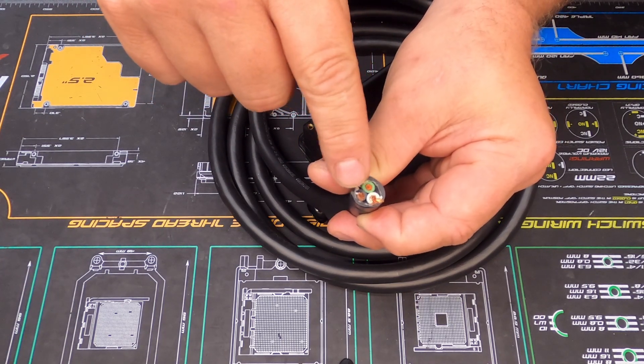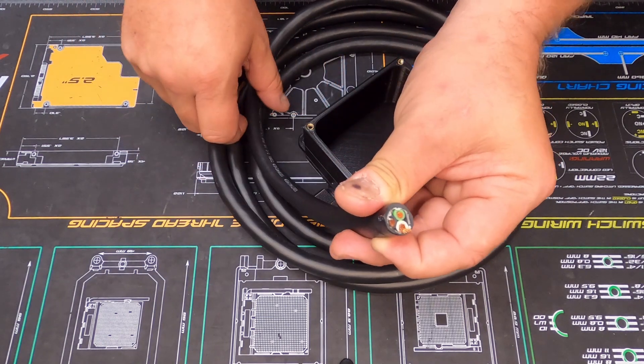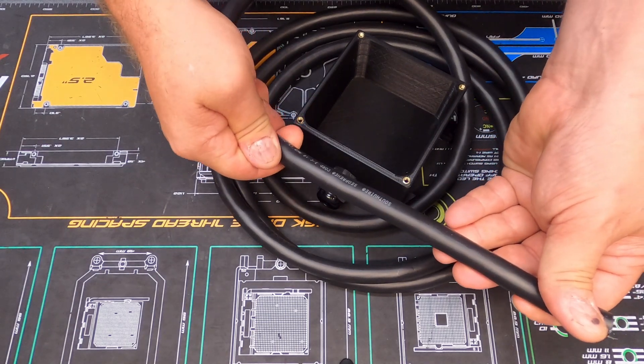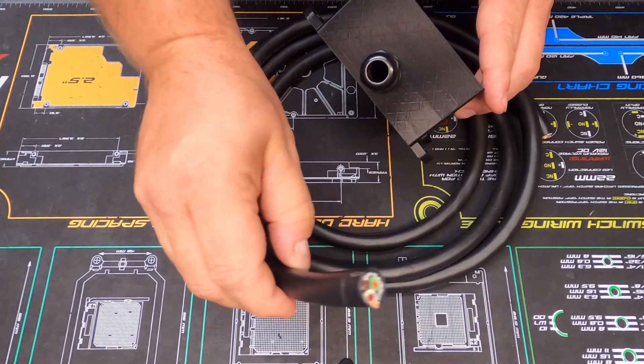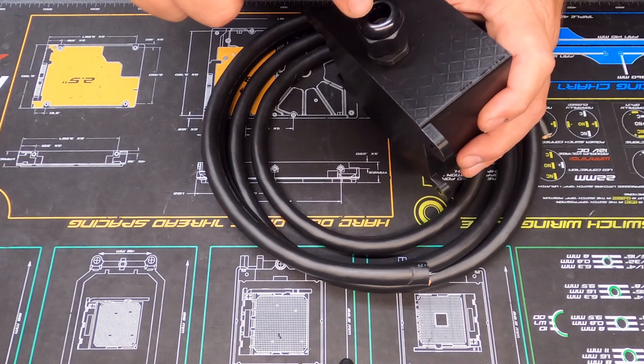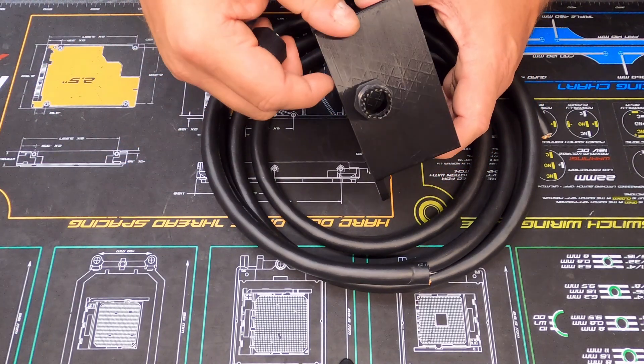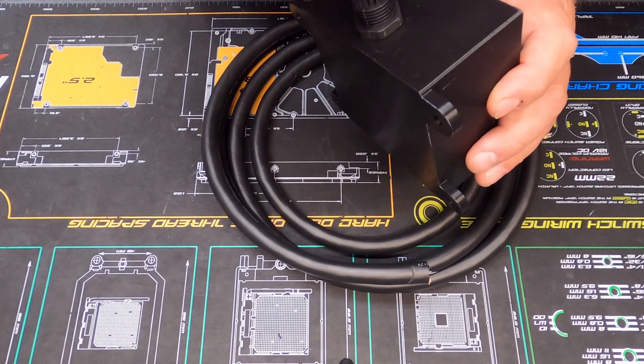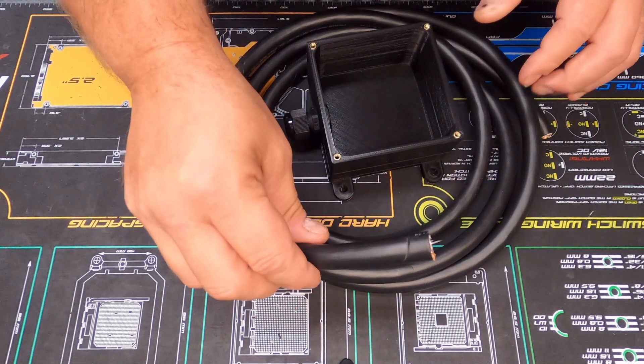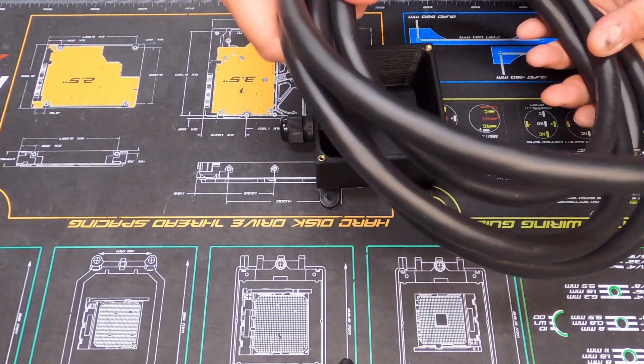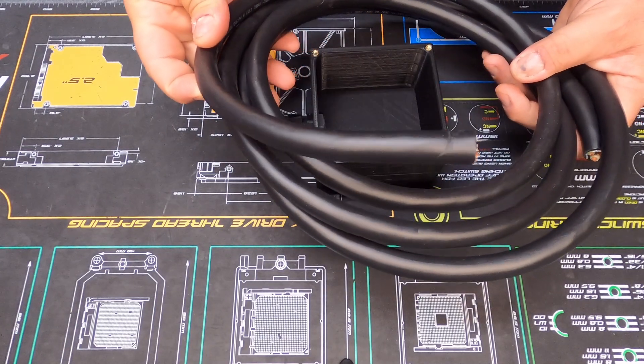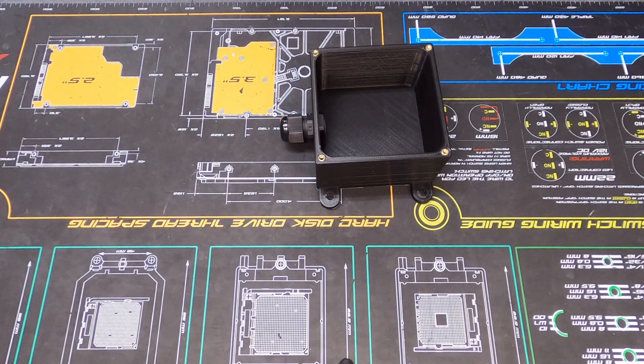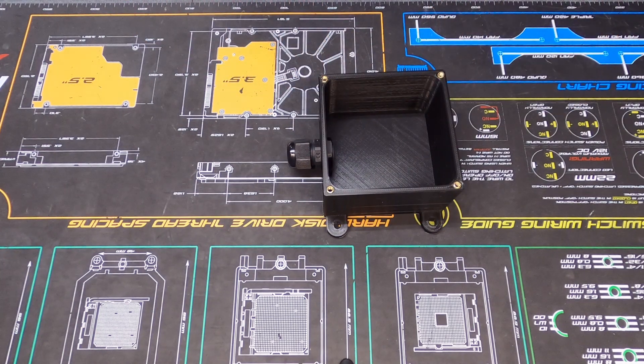The cable that I bought is an extension cord power cable, so it's a 10-2, 10-3. You have especially for the 220 stuff the white and the black for the power and then just the ground for 220. It's really heavy cord. I wasn't sure what size of gland I was going to need with this particular cord, and the 13.5 works pretty well. I'll have to go in and just trim a little bit of the lip inside here to get the cord to go inside there. You can buy this cord at Lowe's - like 20 foot rolls of this stuff for about 35 dollars. It's really heavy and that's what I'm going to use out in my shed. I'm going to start adding some mining rigs here pretty soon I hope.